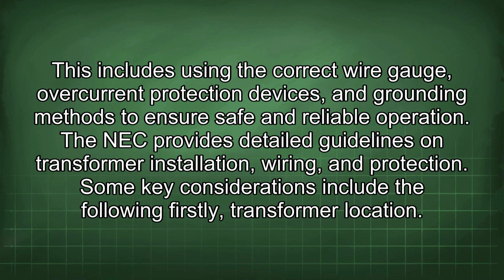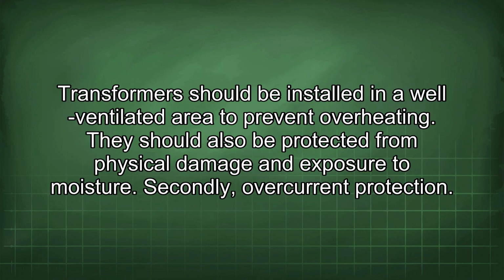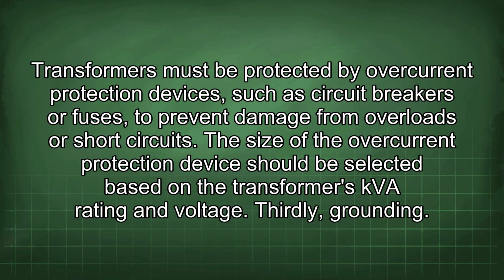Firstly, transformer location. Transformers should be installed in a well-ventilated area to prevent overheating. They should also be protected from physical damage and exposure to moisture. Secondly, overcurrent protection. Transformers must be protected by overcurrent protection devices such as circuit breakers or fuses to prevent damage from overloads or short circuits. The size of the overcurrent protection device should be selected based on the transformer's kVA rating and voltage.